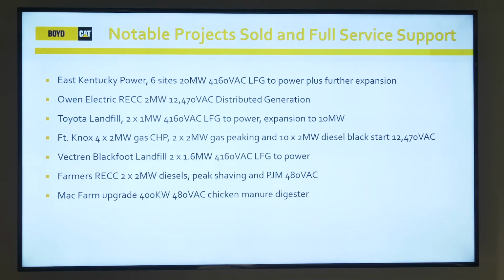That power is generated from the landfill gas. They ran a line 5 miles back to the plant, and that green energy goes directly to the plant. This is probably the biggest project we've done, installed 5-6 years ago. We put in 32 megawatts of power, of which 4 gas 2-megawatt units are running 24/7 in a CHP application, combined heat and power. So we're taking electric off the back end, recovering the exhaust jacket water, providing facility heat. Some of that heat goes through an absorption chiller and is used for cooling in the summer.